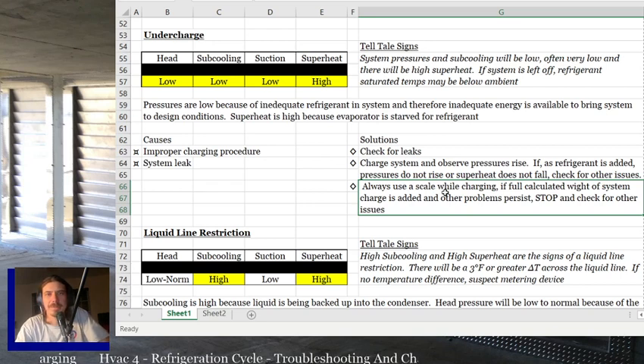Because anytime it's been off for a little bit, whatever ambient is should be what the saturated temperature of the refrigerant is. So if the refrigerant saturated temps are below ambient, if the system is left off, then you're probably low on charge. And when you turn it on, you should see everything's low except for your superheat's going to be high.